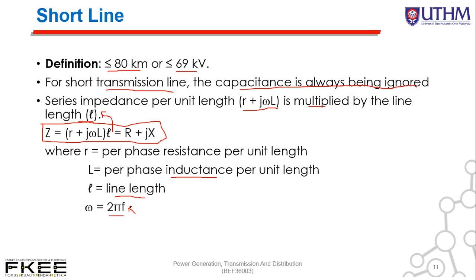So we can calculate the series impedance per unit length, that is R plus j omega L multiplied by the line length. So if the length is 80 km, we can get the series impedance from R plus j omega L times the length L. Okay, so this is the equation for the series impedance, that is Z equal to R plus j omega L times the distance L, equal to R plus jX. Where R is the per phase resistance per unit length, L is inductance per unit length per phase, L is the line length, and omega is 2 pi f. So it depends on the frequency, either 50 or 60 Hz.